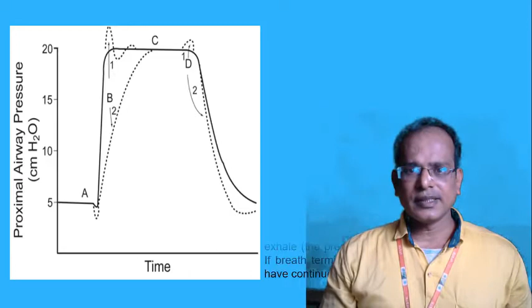This figure shows the characteristics of a pressure supported breath. In this example, the baseline pressure, that is PEEP, is set at 5 centimeters H2O, and the pressure support is set at 15 centimeters H2O. The inspiration is triggered at point A by a patient effort, resulting in a decrease in airway pressure.